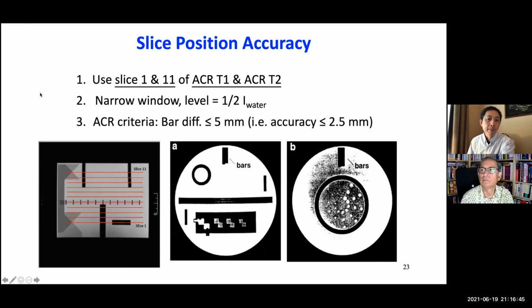Okay, sir, please. Yeah, the next test is about slice position accuracy. Slice position accuracy is based on the two ramps here. We prescribe slice 1 and slice 11 across the ramps. If they are accurate, then the lengths of the ramps should match. But when they do not match, that's a slice accuracy issue. So the ACR criterion is that the bar difference should be less than 5 millimeters. Because the ramps are at 45 degrees, the 5 millimeters represents an accuracy of 2.5 millimeters.